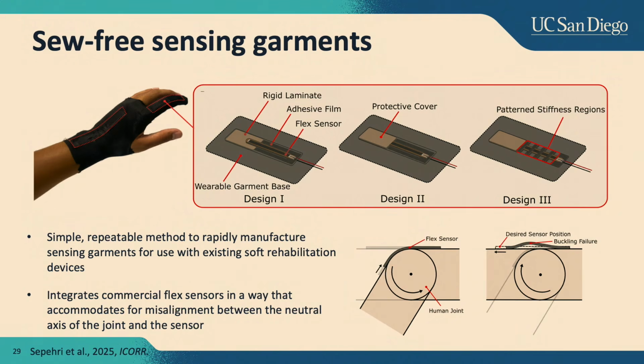And so what we had here is 3 different designs. The first design is quite simple. We have this smooth surface for sliding, and we added a little bit of increased stiffness to prevent any buckling of the flex sensor. For the second one, all we did on top of this was add a spacer and a cover to reduce friction. And for the third one, we tried to add a patterned region, thinking that it would allow for more uniform creasing. We wanted to compare these 3 different designs and compare the calibration curves that mapped our sensor signal to the joint angle, and also look at hysteresis.